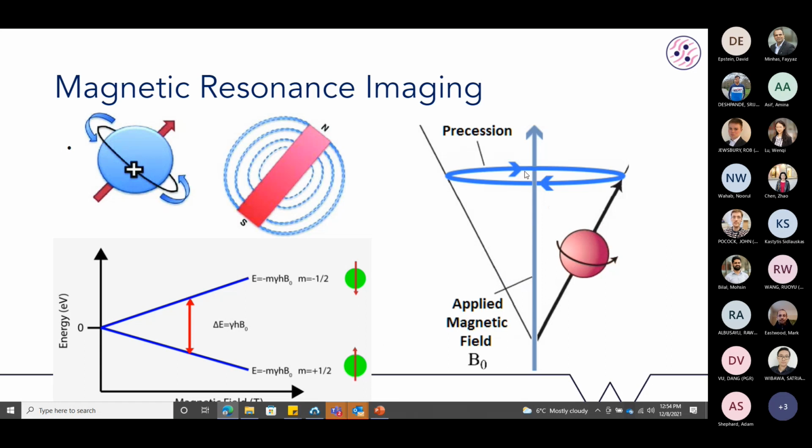It precesses with the magnetic field. Spin down is high energy, precesses anti-parallel to the magnetic field. And it's similar to what Mark's mentioned a few times in his talk, that once you've got these different types of energy levels, you can trigger transitions between energy levels via photons, essentially. And that's the basis of MRI signal. You apply a radio frequency pulse, which can cause excitations to higher energy states, and then when you remove the pulse, it relaxes down to a lower energy state, and you emit a photon as a result, and this is the basis of the signal.